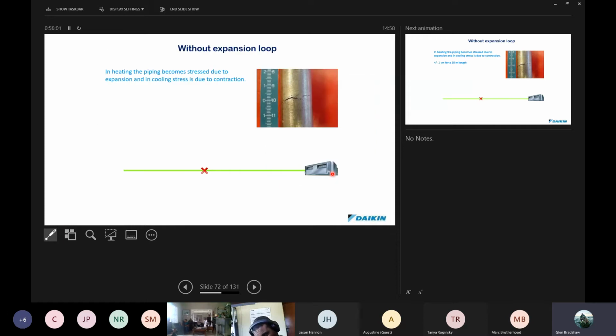Expansion and contraction is easily identified when we have cracks in piping. It's a stress crack from where the pipe is being compressed and expanded, or under tension and compression, and eventually the piping will crack in that manner. We must consider that we are moving piping, and it can go anywhere from 0 to possibly 75, 85 odd degrees. A fair amount of expansion can happen: you can get up to 1 centimeter per 10 meters in length over that temperature range. It's quite considerable, and from time to time you may be required to put in an expansion joint to prevent the piping from cracking or RefNets from being broken.